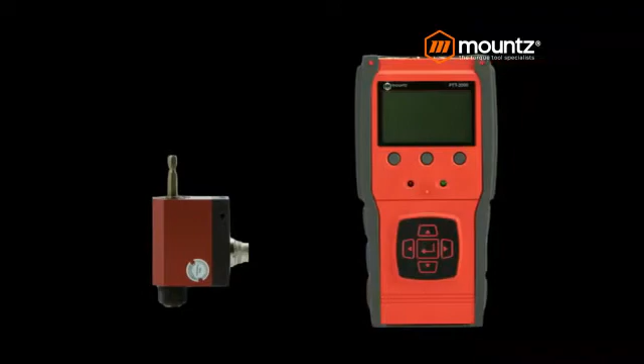So what is a rotary torque sensor, also called a dynamic torque sensor? Well, a rotary torque sensor will, in most cases, work with a torque analyzer, in this case a PTT. The rotary sensor comes in between the tool that is applying the torque and the fastener, here the bit. So it will be directly in line with the torque application, and this will give us insight into what torque is currently applied on the assembly.